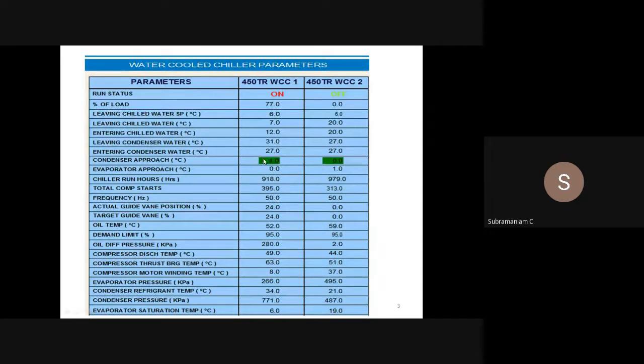This means this is a little alarm. Because if your approach is more, what is the approach? My leaving condenser water temperature and my refrigerant condensing saturation temperature. If that temperature is more, that means my heat transfer is not efficient, which means I am losing energy there. So you will have to start doing descaling. You will have to do chemical descaling and all those kind of things there.